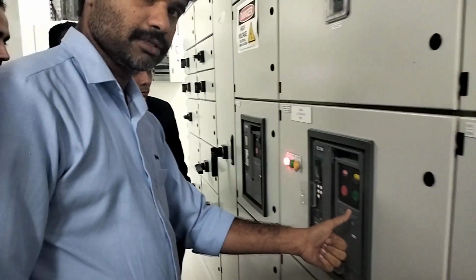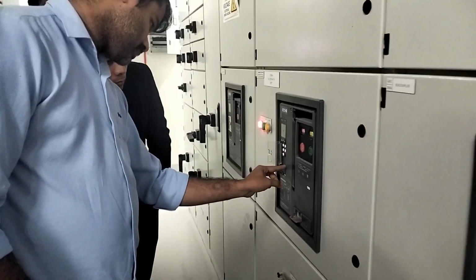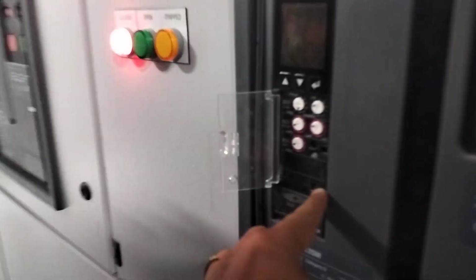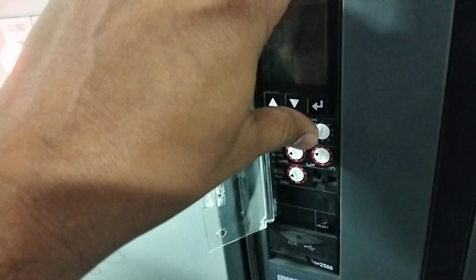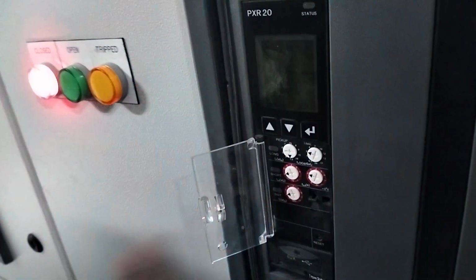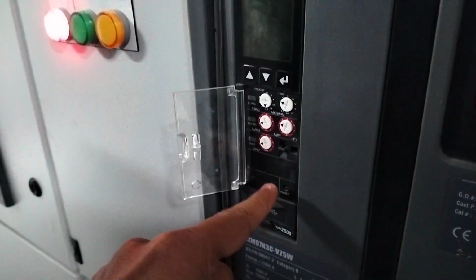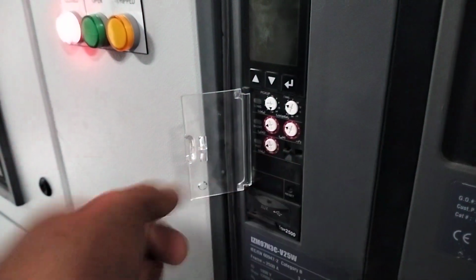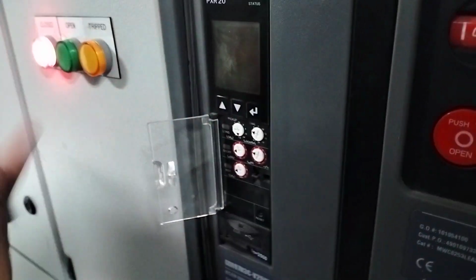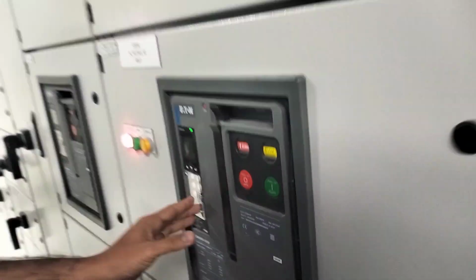Same thing: if something operated here, you will come to know which protection operated. It will come out. You have to reset it, then charge it and close it. Make sure you reset through this small button. If it is not reset, it will still work, but you have to reset it. Without resetting this knob, it won't work. If you do not reset this place, you can switch on, but again it will give you false indications. So we need to reset this also, from here.